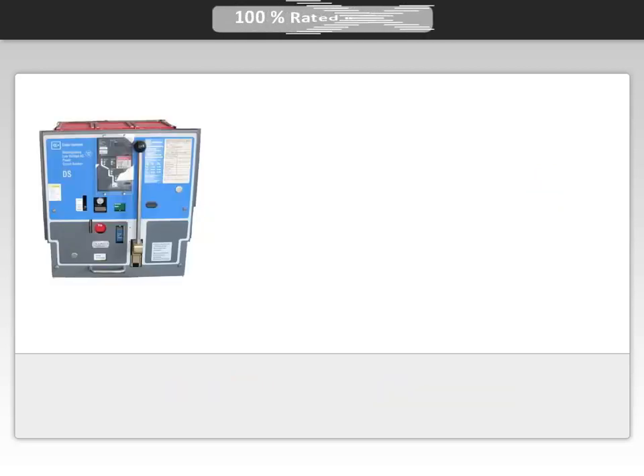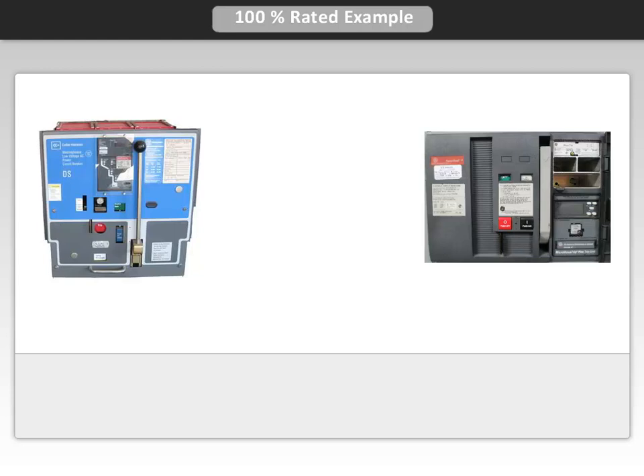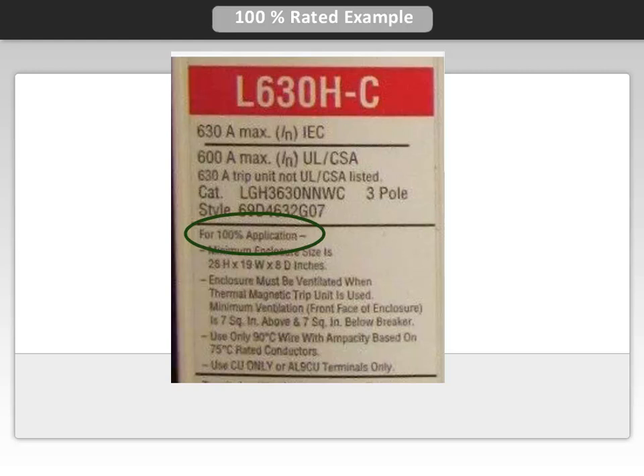Low voltage power breakers and some insulated case breakers are 100% rated. This means the breaker does not need to be derated and can be used at the full breaker rating. Manufacturers of molded case circuit breakers have some models that are UL listed for application at 100% of their rating.